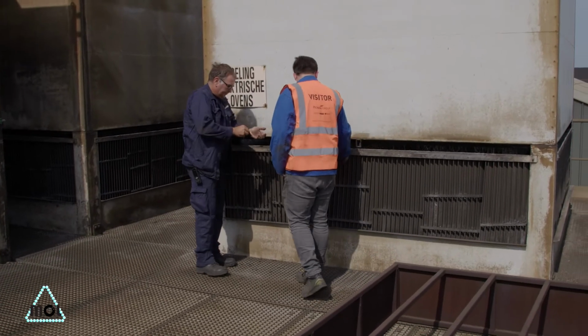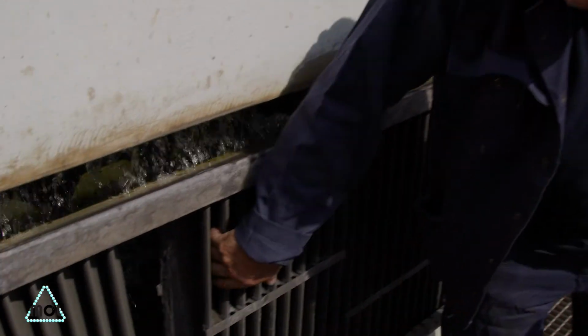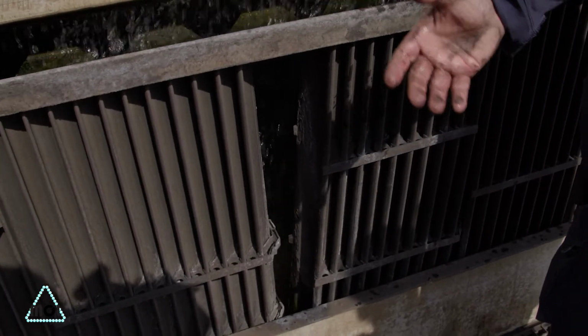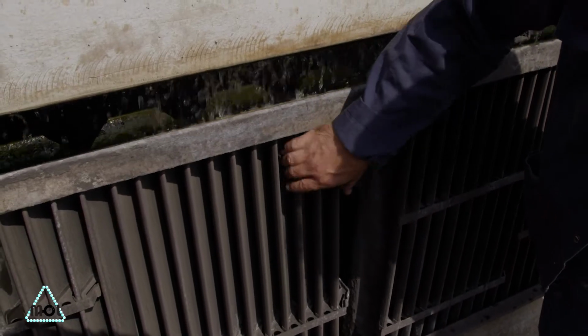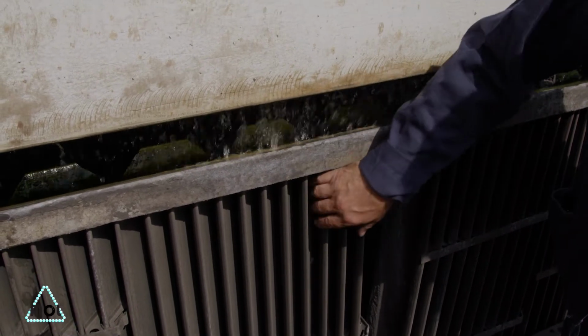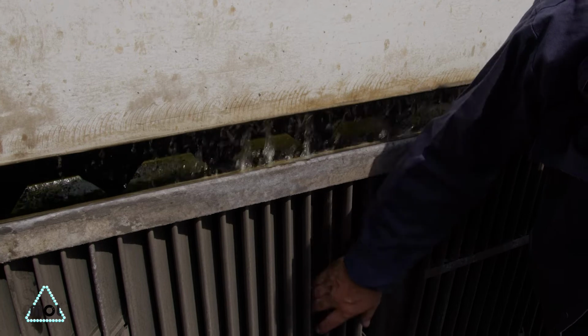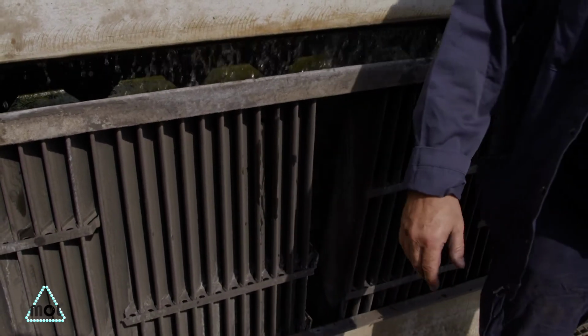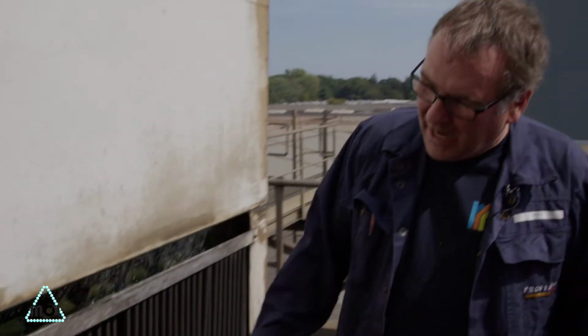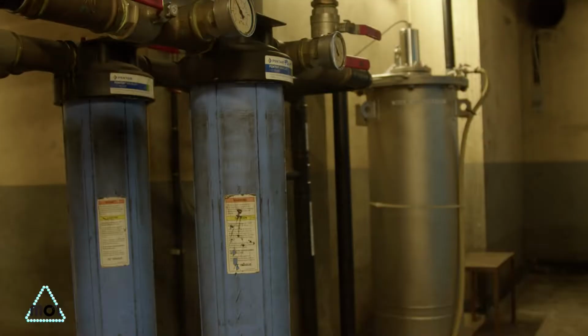Before the water treatment, everything here was green, and these openings were completely blocked, a little bit from dust, but also from the water inside that cooled on the lamels, and it completely blocked the air. We had to clean it, I think, every 4 months with high pressure.